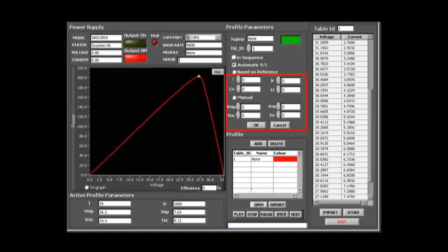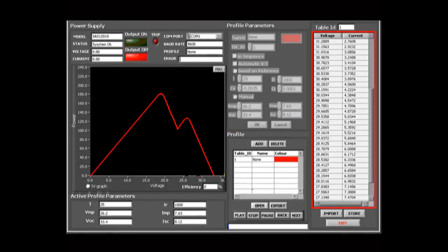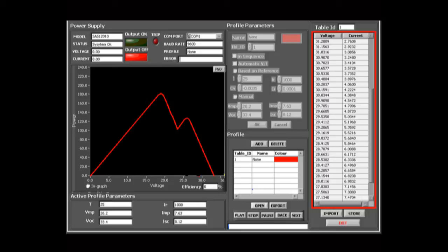Another method for generating a profile is to keep the four defined points of open circuit voltage, short circuit current, maximum power voltage and maximum power current fixed and varying the irradiance and temperature associated. And finally, a profile can be generated by manually defining 50 individual curve points. These curve points can be used to emulate shadow curves. Shadow curves emulate panels that are shaded by clouds, trees, buildings, etc.